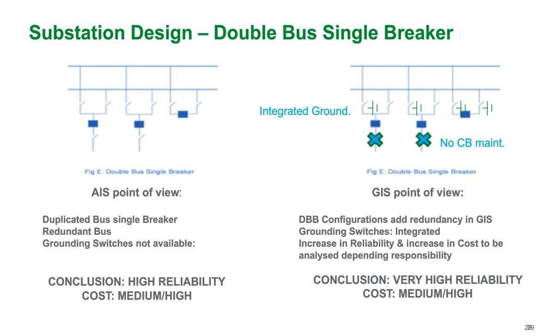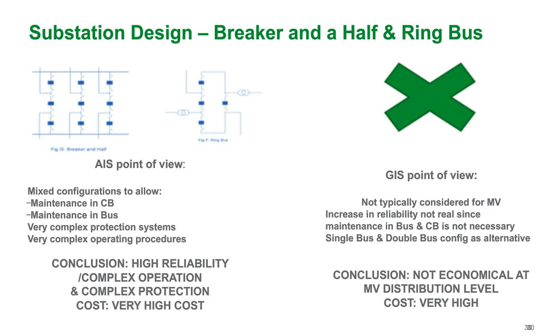Now the last one is a breaker and a half or ring bus configuration. So the main point of this slide is that when we're in the medium voltage arena, typically it's not very economical to have a GIS lineup in a ring bus configuration or breaker and a half configuration, just because of the complexity of the bus bar configuration and the complexity of the protection that's required for this. Typically a ring bus and a breaker and a half scheme is something that would be more cost effective and of more use in the high voltage arena, so at a high voltage substation.